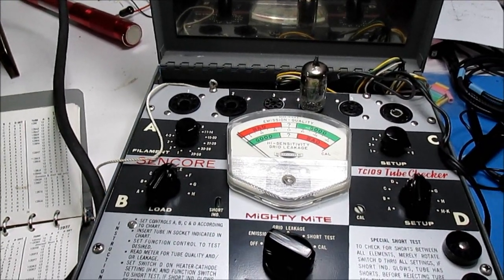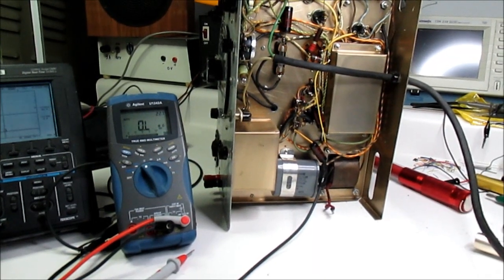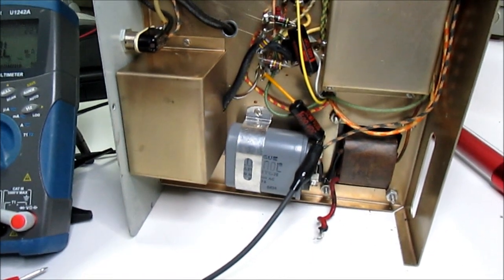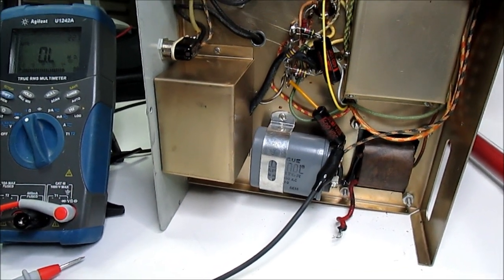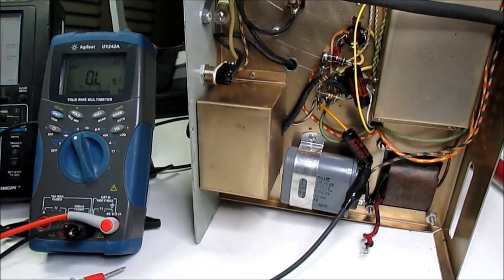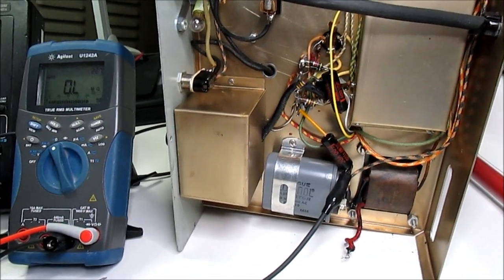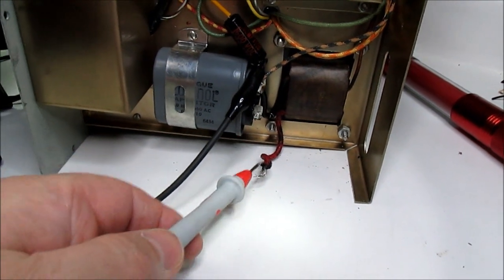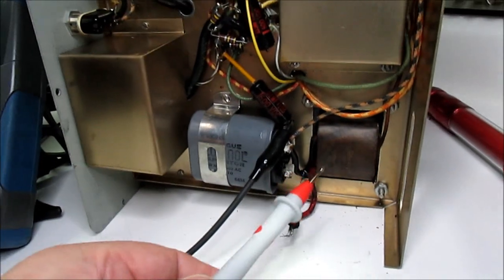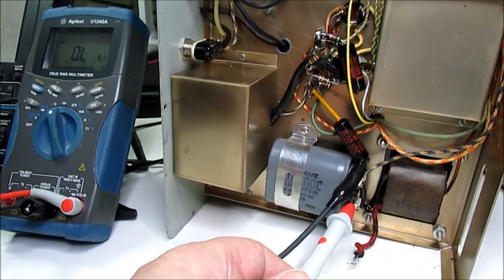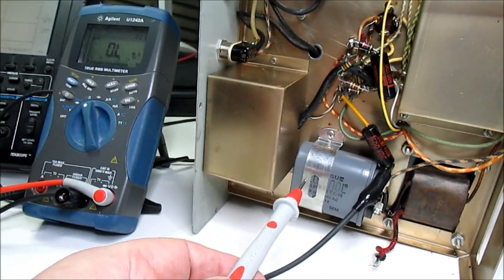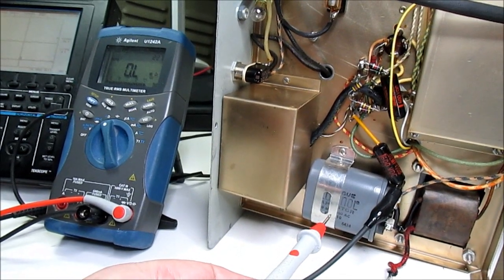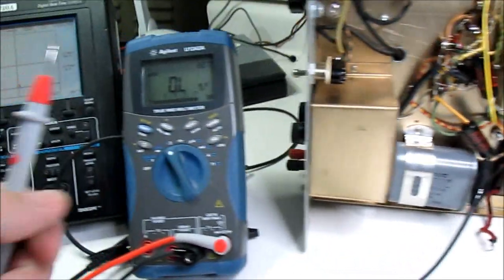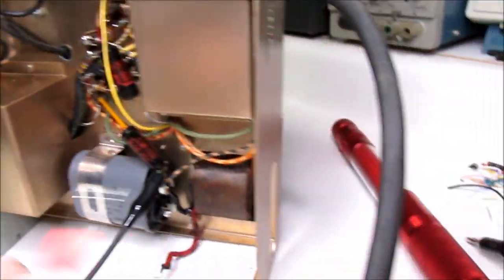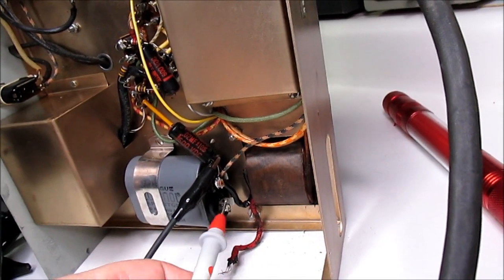And we need to look at a few other things. All right. So I had some suspicions about this oil-filled, or what I think is oil-filled, AC capacitor across one of the windings of the transformer that I think is hotter than the other one. So I've unsoldered the wire on one end of it, and we're going to use the capacitance test on my DMM to check the capacitance across this thing. If you recall from the parts list, it's a 1 microfarad part at 660 volts AC. So we're going to set that at capacitance, and we have our other end connected to one terminal. The other one's completely open, so we're going to hook that up and see what we get.